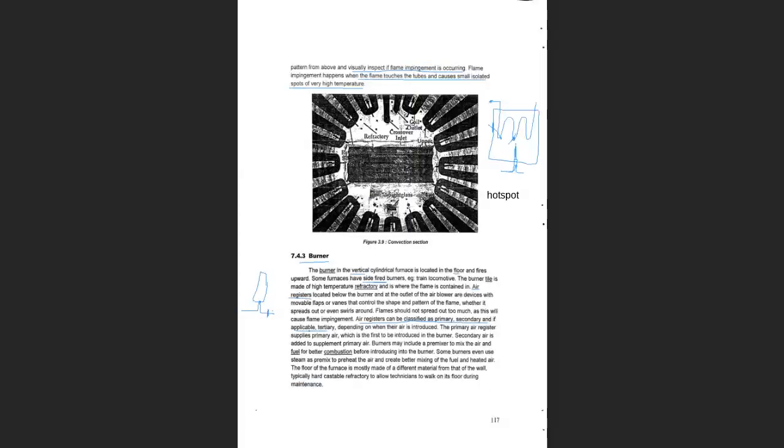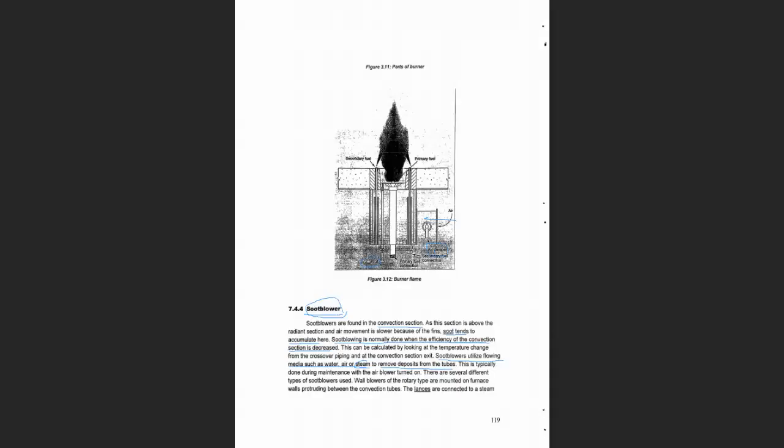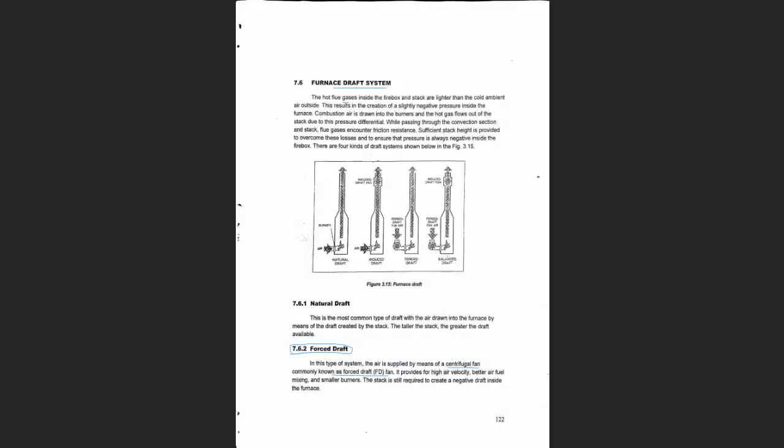طبعا for your information guys, usually most of the furnaces are not designed to have a forced draft. السبب اللي ذكرناه قبل شوي أنه you need to inspect the coils and the wall of the furnace. You cannot do that with the pressure inside the furnace being above the atmospheric pressure. فالفورس درافت عادة ما يستخدم في الأفران، يستخدم في البويلرز أغلب الأحيان. جميل. خلونا نشوف الصورة هنا، this is the forced draft. You have a fan that forces air or compresses air. فالبريشر هنا داخل يعتبر above the atmospheric pressure.